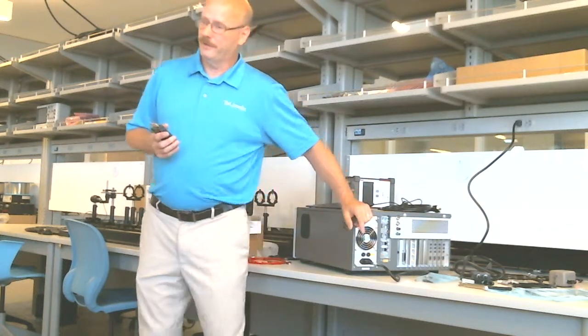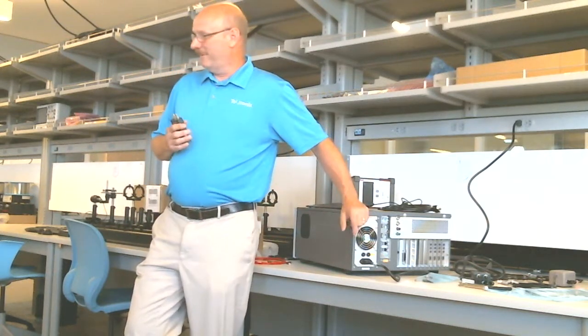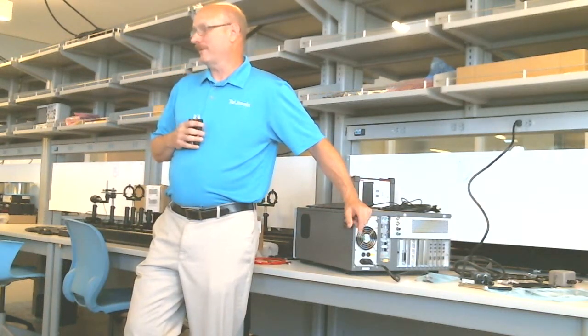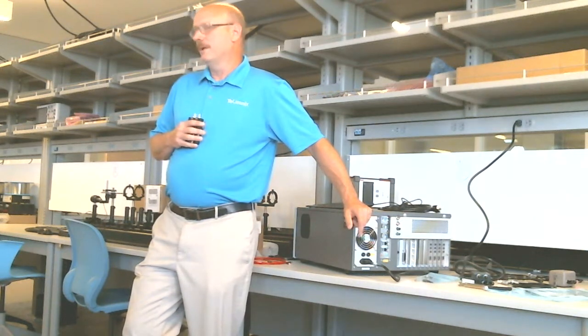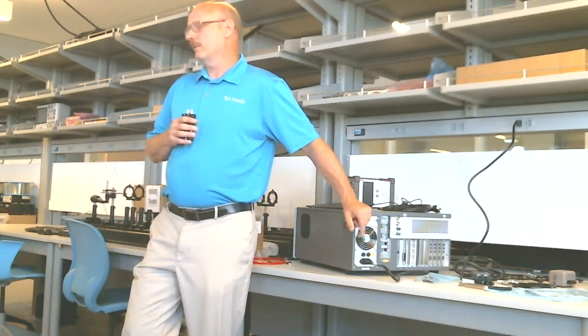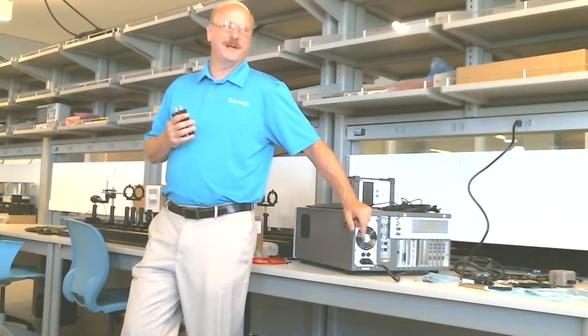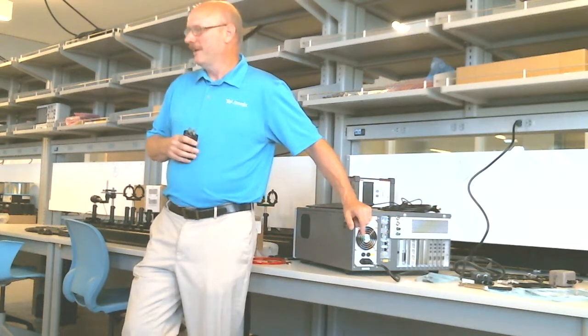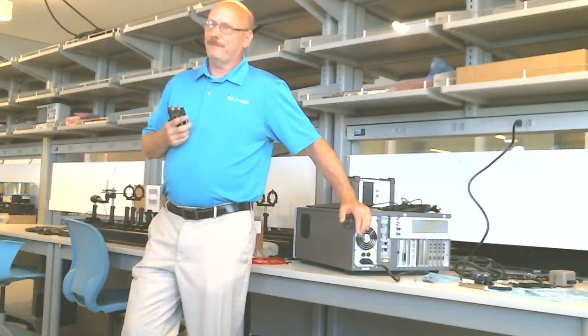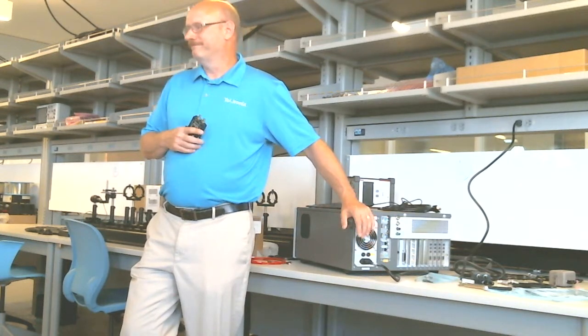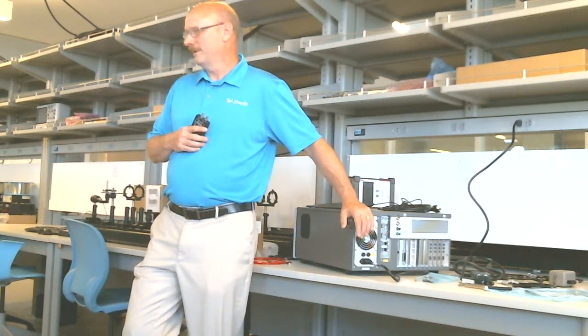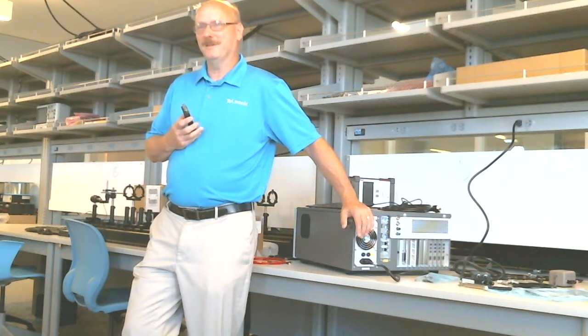If you need to calibrate, it's got to go back to the factory. We can do on-site calibration, but you're not going to want to pay for it, it's very expensive. We have to bring somebody out here with all their equipment. A lot of people think they can calibrate these themselves, but you're not calibrating nano amp levels occurring here, it's not going to happen.